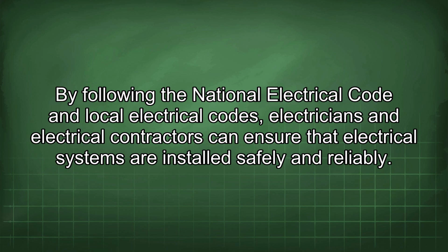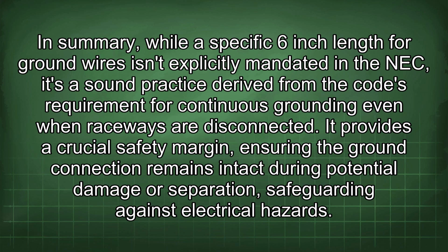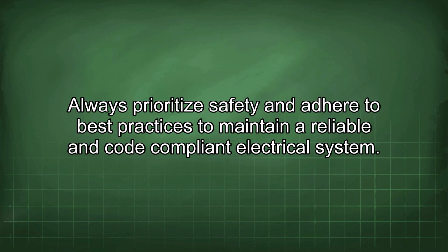In summary, while a specific 6-inch length for ground wires isn't explicitly mandated in the NEC, it's a sound practice derived from the code's requirement for continuous grounding even when raceways are disconnected. It provides a crucial safety margin, ensuring the ground connection remains intact during potential damage or separation, safeguarding against electrical hazards. Always prioritize safety and adhere to best practices to maintain a reliable and code-compliant electrical system.